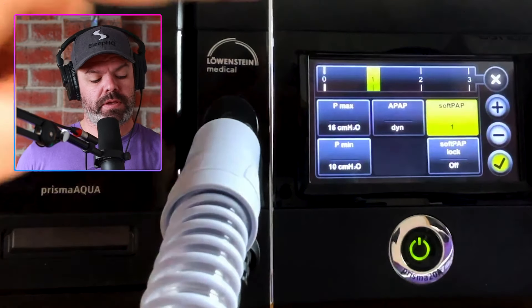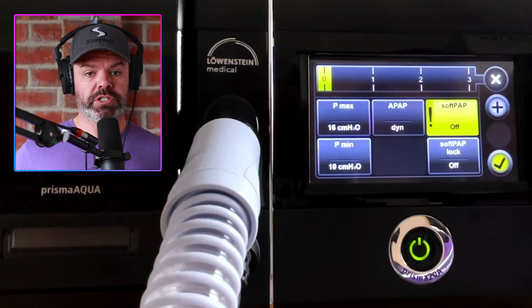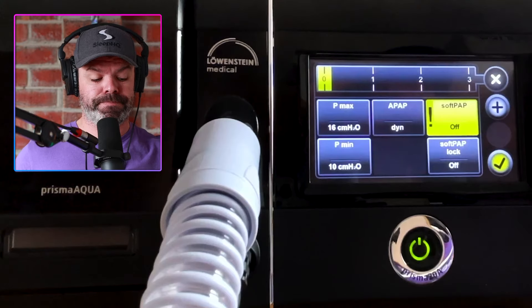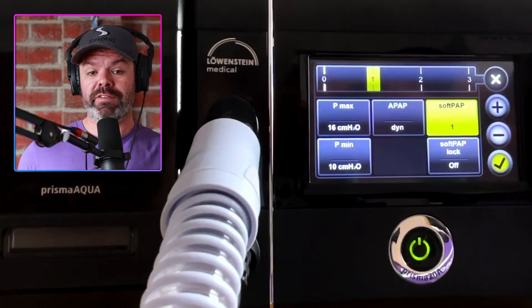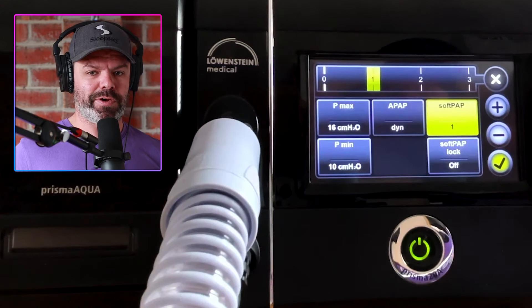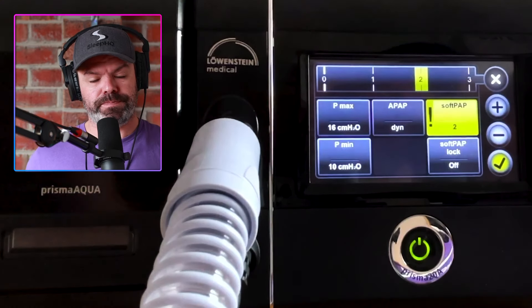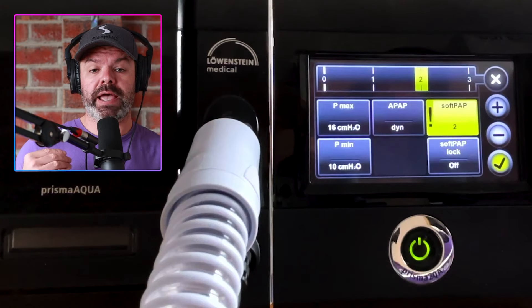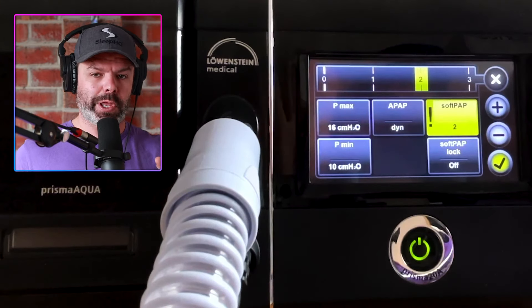When Soft Pap is on zero there is no exhalation pressure relief — inhalation and exhalation pressure are the same. At level one we have a mild level of exhalation pressure relief. Moving up to level two we have a moderate level; when we exhale, the pressure delivery will be reduced by a moderate level, around two centimeters.